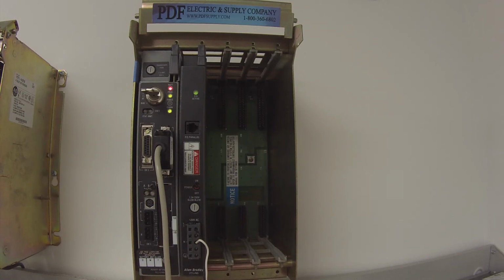Well, a couple things. Before we get to the Ethernet, we want to check the processor status. So on the left hand side, you can either right click on processor status and hit open, or double click on it. And it'll say file S2 status. It's got a bunch of different tabs. It's a window that pops open with tabs at the top. And the one I'm going to go to as you're going to the right hand side is errors. This is going to show me if there's any current errors with the processor.